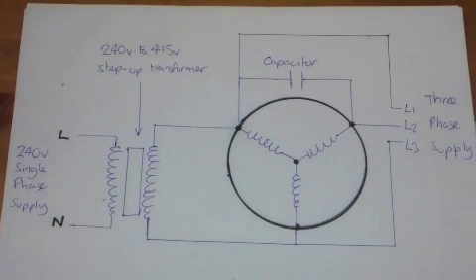The capacitor helps this one along and helps it to be strong and from these three connections that we've made wires to we take our supply lines off to become our three phase supply and they are L1 L2 and L3 and this is getting quite close now you've got 415 volts between each of the phases however again there's no neutral.